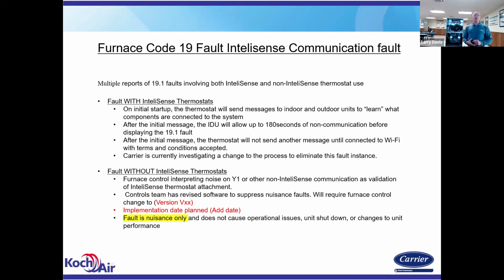This came up, a question came up earlier. Fault code 19 on the mid-tier or non-communicating, if you're using a communicating system on a non-communicating wall control, if you are not using the IntelliSense thermostat, that's the specific thermostat that allows that IntelliSense process to work, you'll get a code. It's like 19.1. There's some thermostats that you definitely don't want to use a power robbing thermostat on these furnaces. You're going to have all sorts of problems. Or a battery powered thermostat is going to give you some problems. You really want to go to a 24 volt with a common thermostat for these.